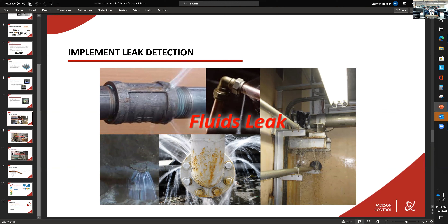So fluids damage, fluids cause problems, and with our leak detection, fluids are detected. Ultimately, we want to help minimize massive problems and destruction of different property by providing early detection. And again, with a variety of our systems that we'll show as well, with our relay output or connected integrated into your automation system, it's not terribly difficult to make a water valve close, to shut that water off, get the alarm out, shut the water off, make sure that everything's not gushing for 3 days.